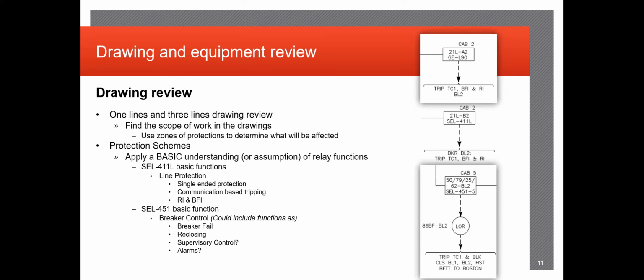Reclose initiate is primarily associated with breakers themselves. The reclose initiate function is for a one-off type control for the breakers. So in the situation where a fault may occur, whether it be a tree down the line or something happens on the buswork, whatever, the breaker would open because it sees a fault. If that fault immediately disappears and was just a one-off type thing, the reclose initiate would actually kick back in. The breaker would close back in, and if it sees good phase angles and proper current and voltage measurements, then it would stay closed. But the other nice thing about the reclose initiate function as well, if that fault does not leave and there's still an issue, when that breaker closes back in, it just trips out and it will not keep closing and opening over and over again.